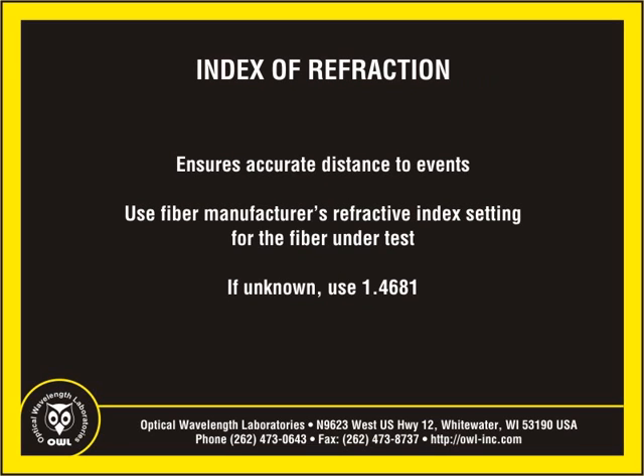To ensure the most accurate distance to events, index of refraction should be set to the fiber manufacturer's refractive index specification for the fiber under test. If unknown, set the index of refraction to 1.4681, as this value falls within 99% of the index of refraction values for most optical fibers.